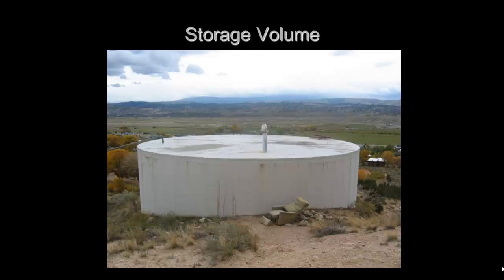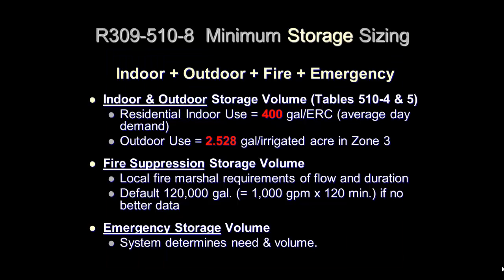We'll now cover the requirements for storage capacity. Drinking Water Rule R309-510-8 provides the requirements for minimum storage sizing. This includes the volume of storage required for indoor and outdoor demands plus fire demands and emergency storage if required. Tables 510-4 and 5 provide the indoor use values for equivalent residential connections or ERCs. Storage for residential indoor use is a minimum of 400 gallons per equivalent residential connection. The storage for outdoor use is dependent on which irrigation zone the system is in. Using Zone 3 as an example, the required volume is 2,528 gallons per irrigated acre. Storage for fire suppression is based on the requirements from the local fire marshal for flow and duration. As a default, 1,000 gallons per minute for 2 hours — which equals 120,000 gallons — is required if no precise data can be determined from the local fire marshal. Emergency storage would be a requirement determined by the system or their engineer.